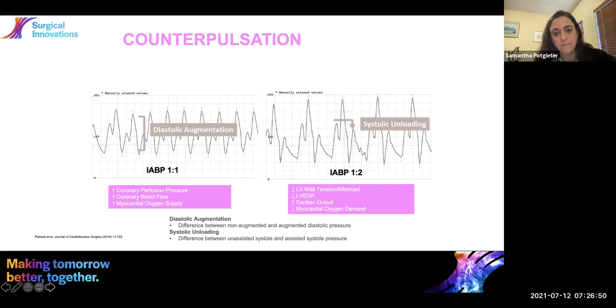Right, important for you to just understand when you do have a patient with you in terms of timing and trigger and what's actually going on in the screen in front of you, what the pump is looking for, what the software is triggering on, and what the timing is doing. So your balloon is synchronized with the cardiac cycle. And the timing is where the balloon is set to inflate and deflate using the arterial waveform. And the trigger is the event that signifies the beginning of a cardiac cycle.